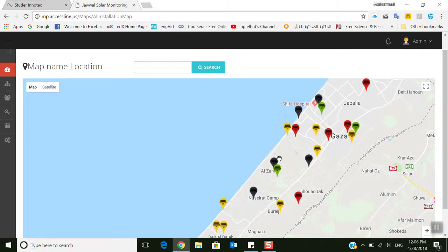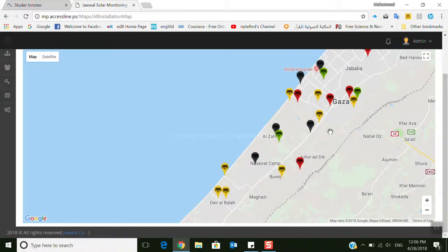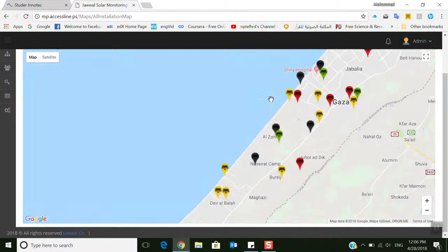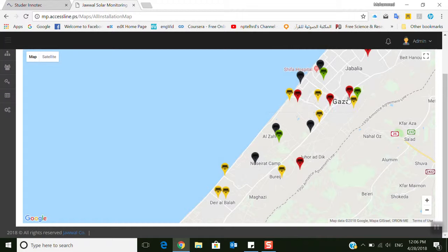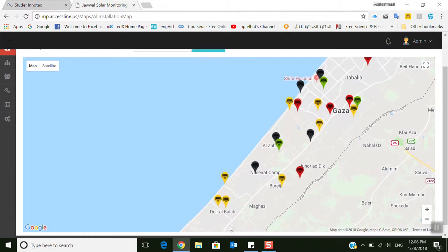We cannot monitor them unless this connectivity issue is solved, and we suffer this connectivity problem: Studer, XCOM, and GSM sometimes lose connectivity and do not connect back, do not make an automatic connection again. This is a very serious problem that we have faced with Studer equipment.